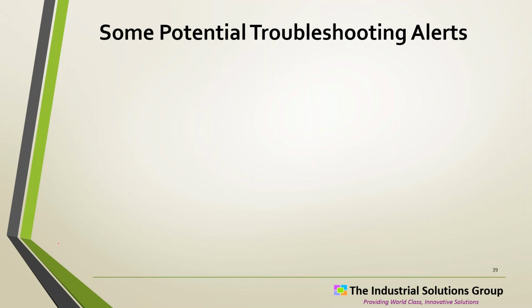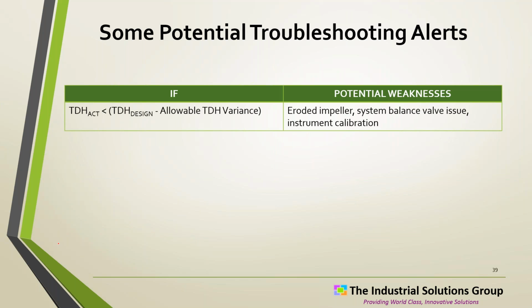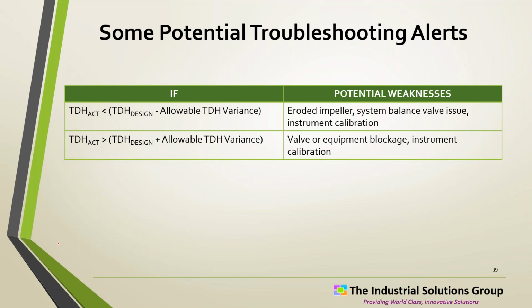So here are some potential troubleshooting alerts that we can do with a pump, and we've done this at a project that we did a few years back out at the Cincinnati airport. We can look at total differential head. What's the actual, and is it less than the design minus that allowable total differential head variance? Well, if it is, we know then we can start informing people, informing the technician, maybe you got an impeller issue, it's going bad, or maybe there's a balancing valve issue, or maybe they got some instrument calibration problems.